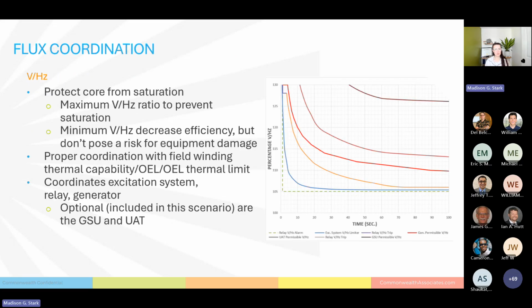The last element that we'll touch on for synchronous generators is called flux coordination. So this is your volt-hertz coordination for your system. So what is flux? Great question. They have entire courses on it. The purpose of this, though: flux involves the changing magnetic field. So the flux is the measure of the changing magnetic field. The magnetic field that's induced by the field windings as the rotor turns generates a magnetic field, and we're measuring that indirectly through the volt-hertz measurement.